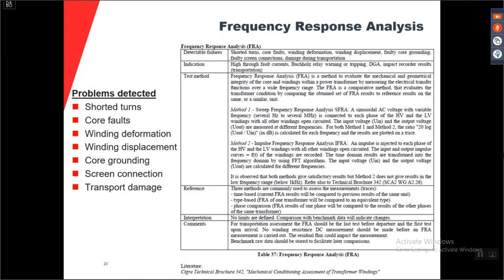For this purpose, it is always good to do a demagnetization. For those of you who attended part 1 and listened to that one, you might remember what I said here. They say don't do winding resistance before any test. I say do winding resistance first and then demagnetize. Because after you have demagnetized, you know the state of your transformer and you know that you have no residual magnetization in the core. And all the following tests will be okay, such as the excitation current, the turns ratio test, the SFRA measurement. That can be very affected by a magnetized core. So the technical brochure says one thing, I say slightly different, but we both have the same aim: to get as good data as possible.